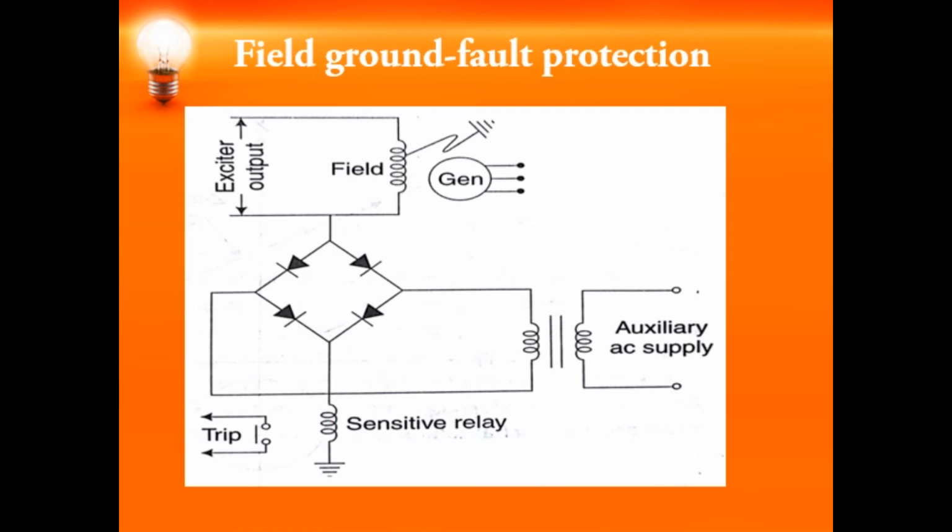For that, this is the schematic diagram of the protection employed for rotor protection, the rotor earth protection. A DC voltage will be applied across the field and with respect to the ground through the help of a polarized moving iron relay. Whenever a single ground fault has occurred, it is not necessary that the relay has to operate and trip. But if a single ground fault has occurred, it can give an alarm.